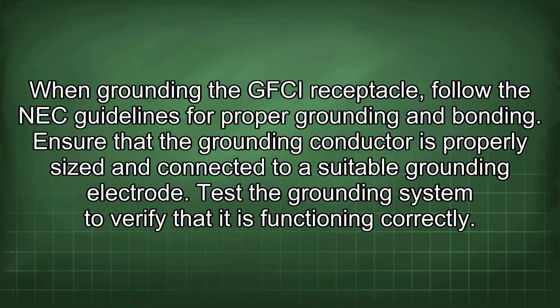When grounding the GFCI receptacle, follow the NEC guidelines for proper grounding and bonding. Ensure that the grounding conductor is properly sized and connected to a suitable grounding electrode. Test the grounding system to verify that it is functioning correctly.